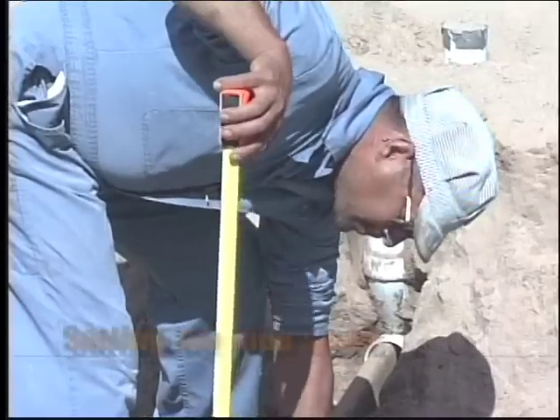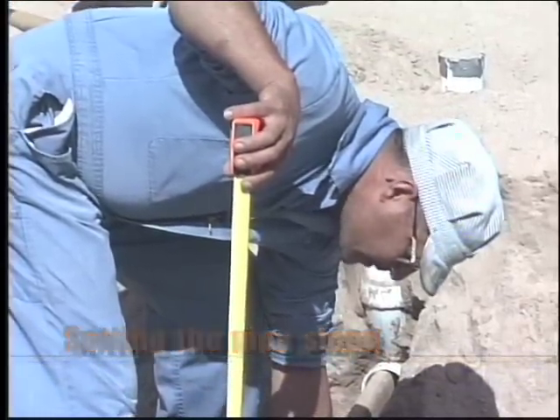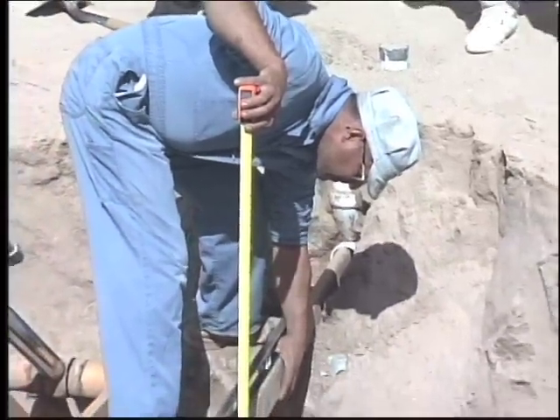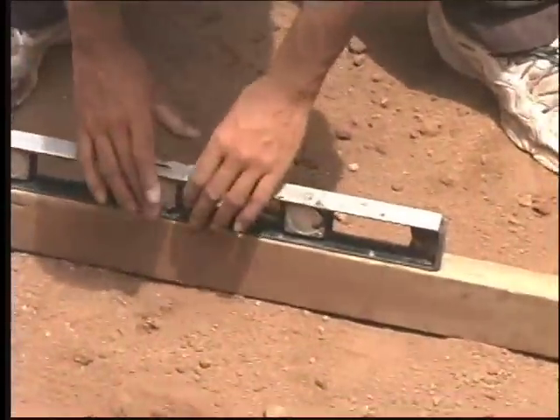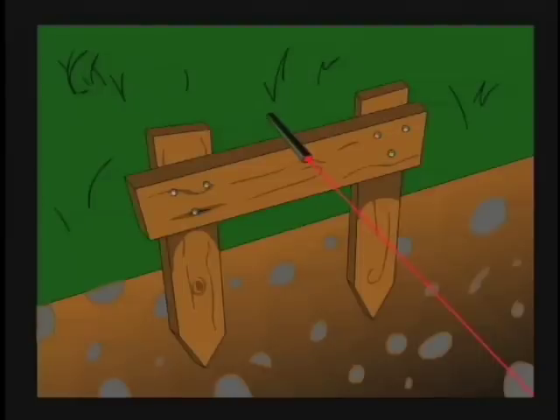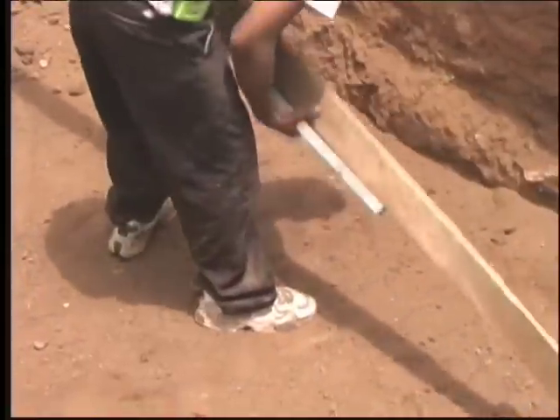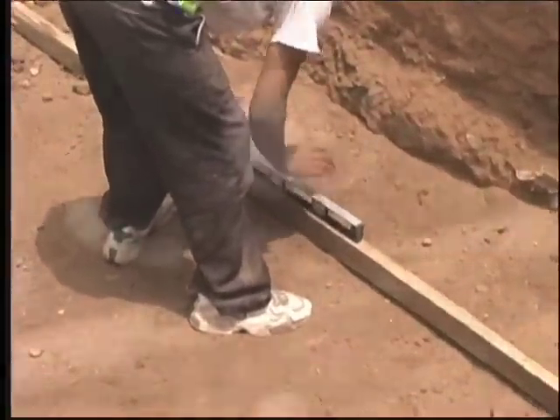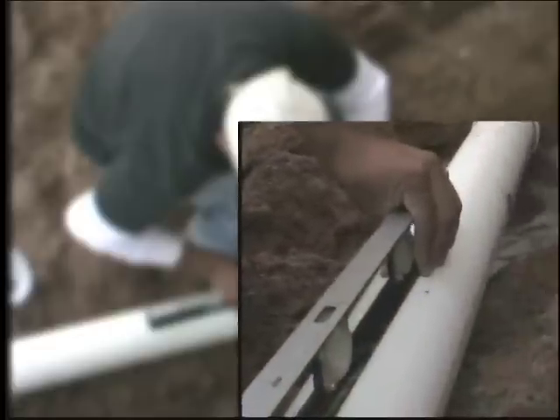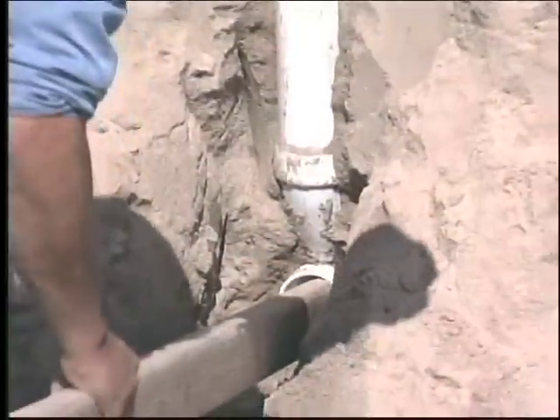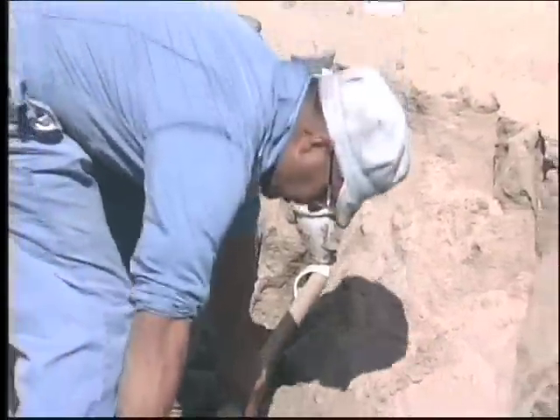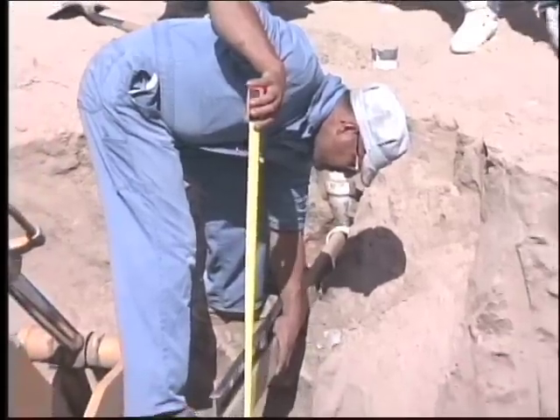The available methods for setting the pipe slope from the house to the septic tank will use one of the following: carpenter's level with 1/4 inch per foot grade mark, string level, water hose, torpedo level with laser pointer, batter boards, 2x4s. The most common technique is the carpenter's level with 1/4 inch per foot grade mark. Insert a section of 2x4 into the end of the 4-inch pipe coming from the house. Place the carpenter's level along top of the 2x4 and adjust the slope so the bubble just touches the line closest to the pipe.